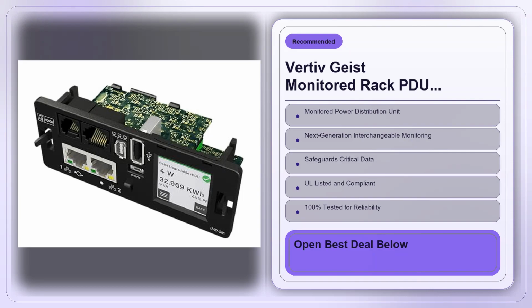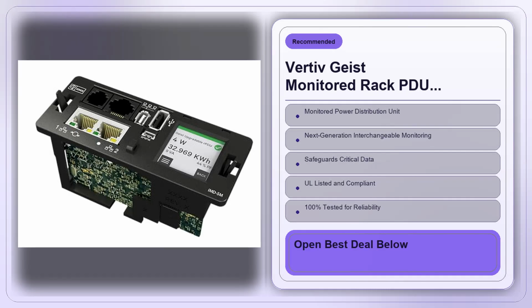Also, the 30 amp rating, while solid for many deployments, can become a ceiling if you're planning to push high-density servers that each draw close to 8 amps. In that scenario, you'd need 2 PDUs or a higher capacity model, which adds cost and complexity.